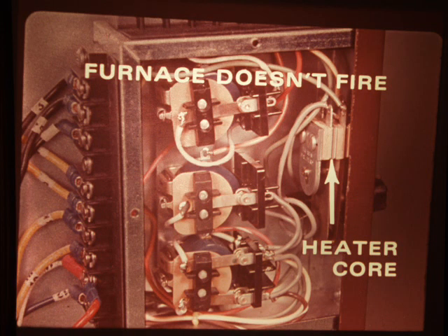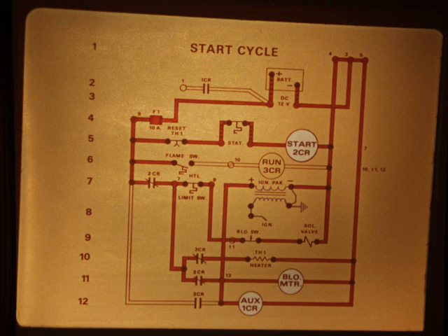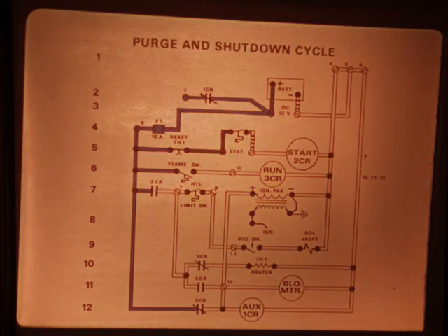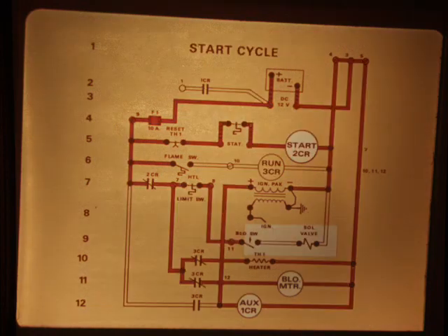Let's see what can happen now if something goes awry. Suppose the furnace doesn't fire for some reason. Remember, in the start cycle, we're applying power to a heater coil on the thermal reset relay. If the burner doesn't come on, or if we have a poor flame, the flame rod doesn't heat up, or it heats up slowly. That delays the energizing of the run relay. And about 35 to 45 seconds after the start relay comes on, the heater warms the thermal relay enough to pop the reset. The unit is shut down.